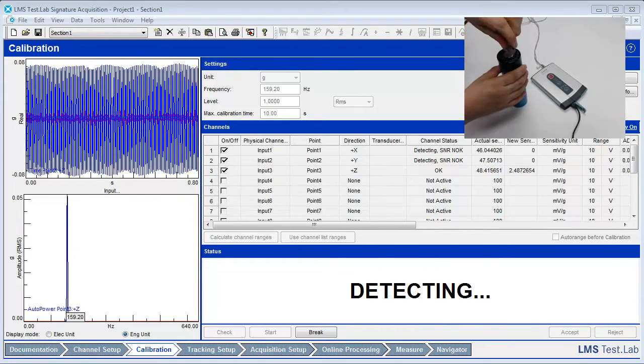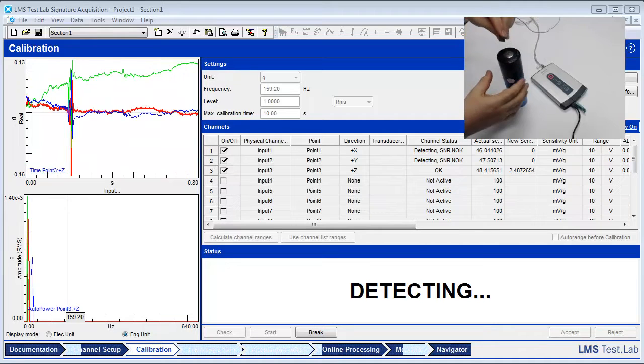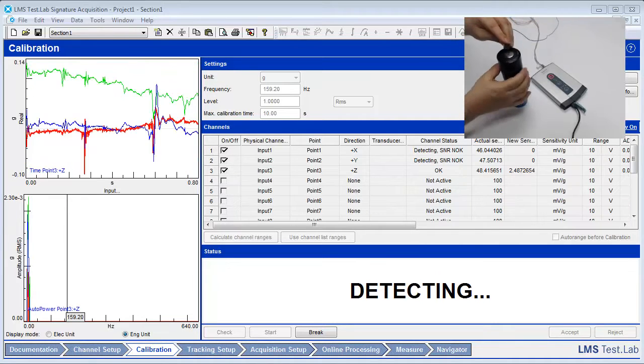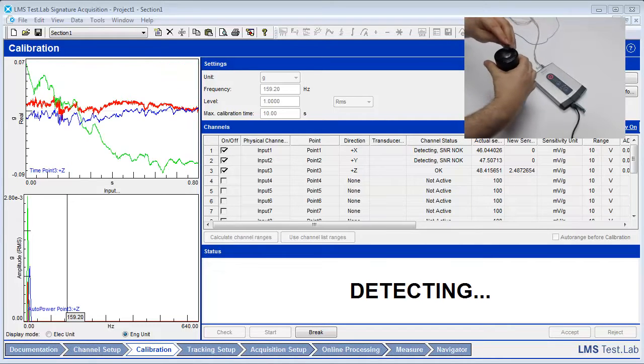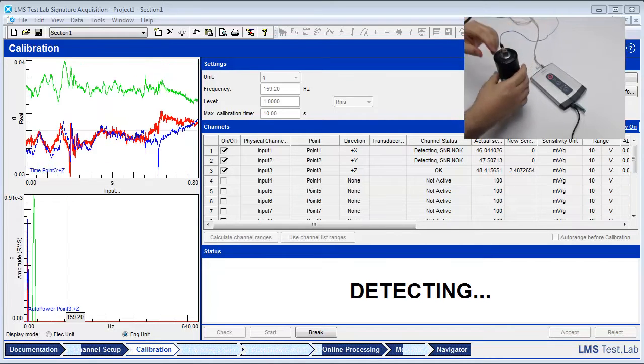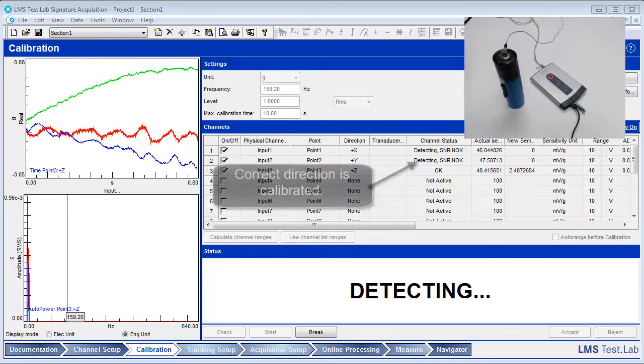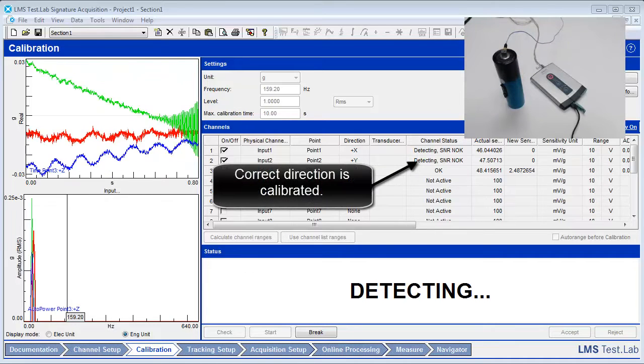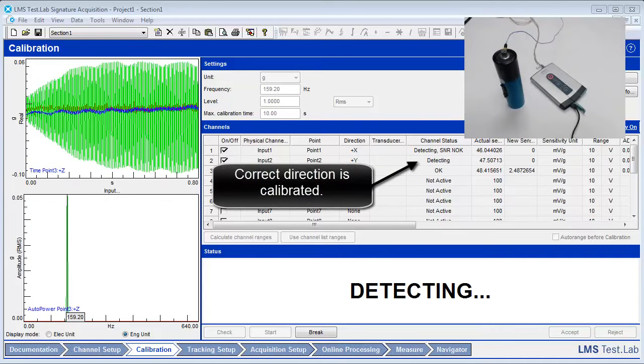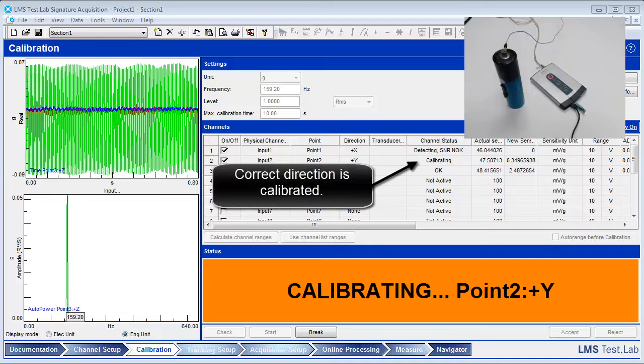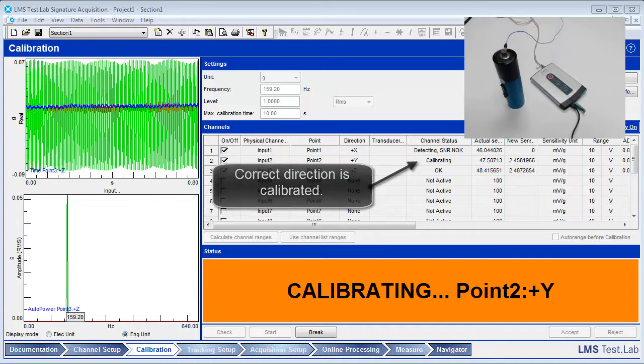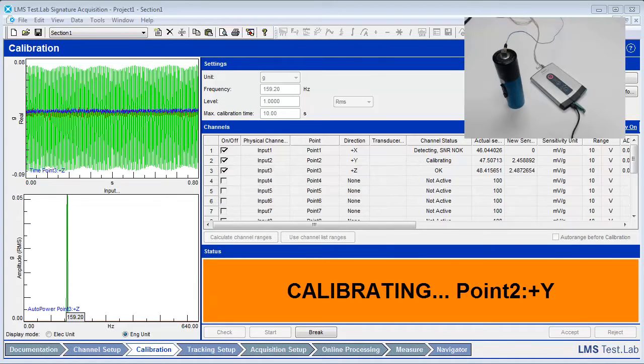After the first direction has been calibrated properly and the message area turns to Detecting, turn off the calibrator. Rotate the accelerometer so that a different direction is facing up and turn the calibrator back on. Do this until each direction of the accelerometer has been calibrated.